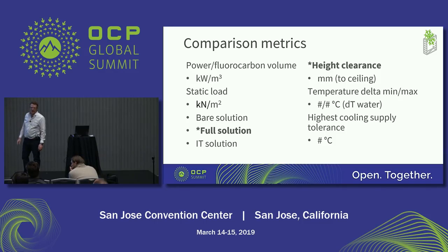All right, temperature delta. This goes into the cooling layout, the water infrastructure, or the facility coolant infrastructure. Yeah, cool. What's the delta T? A cooling infrastructure is usually laid out for a certain delta to maximize the efficiency of either chillers, dry coolers, whatever strategy is applied, adiabatic, doesn't really matter, or even reuse. But still, to maximize that efficiency, you might want to know, especially with thermal optimized systems, what delta can be maintained automatically.